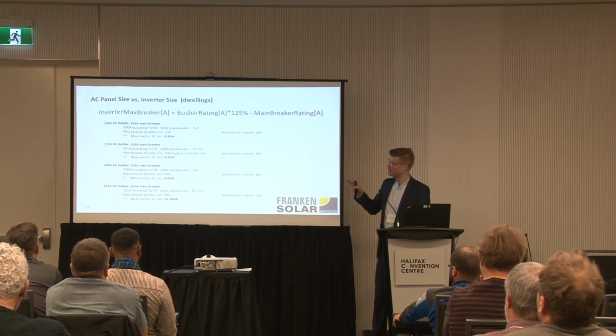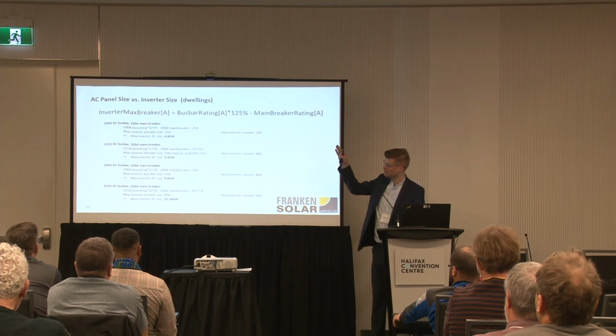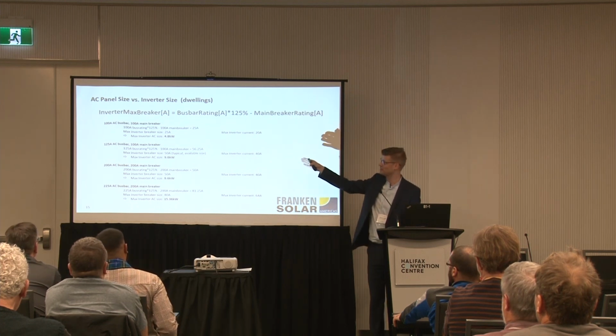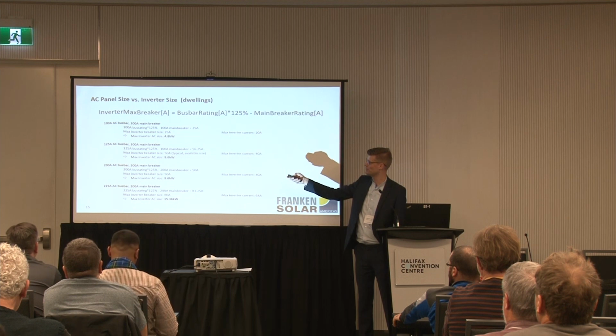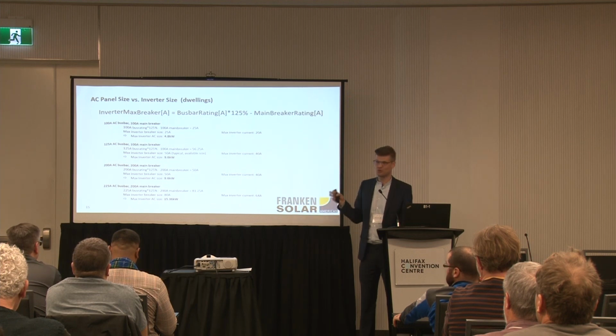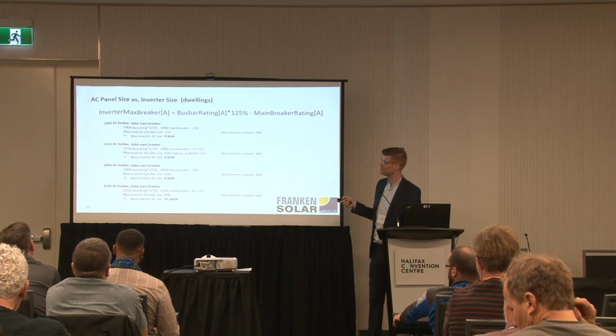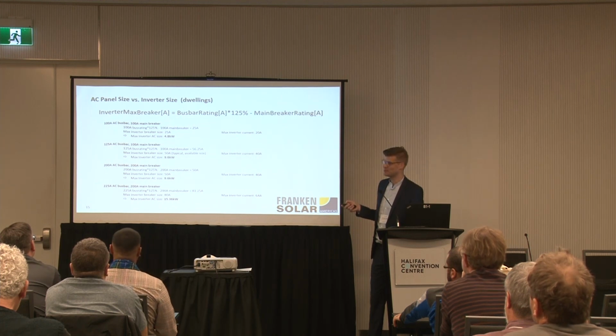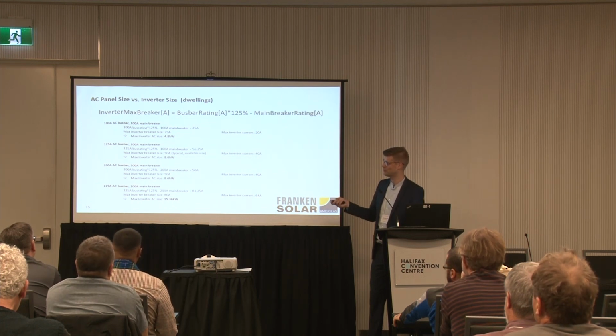As a very quick overview, I have the four most common combinations. We have the 100-100 as the top. That can only give you about a 4.8 kilowatt inverter. That doesn't really exist at the moment. The 125 is already a more suitable option. You can go up to 9.6 kilowatts. And if you have a 200 amp busbar, as we just did the math, you can go to the same 9.6.